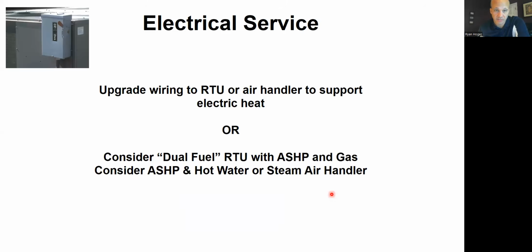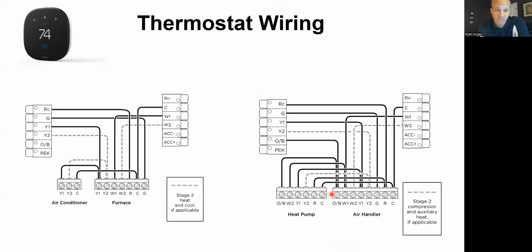And I'm going to go back to last week, just for anybody who wasn't on. When you have an AC system, you typically have 1, 2, 3, 4, 5 wires. Up top here is the thermostat. Five wires from the thermostat down to the furnace or the air handler. When you go to a heat pump, you have 1, 2, 3, 4, 5, 6 wires. You need one extra wire because of the reversing valve. So if you went from single stage AC to single stage heat pump, from the thermostat to the fan coil or air handler or furnace, you need one more wire than you used to have. And maybe you've got a spare wire in the wall, maybe you don't.